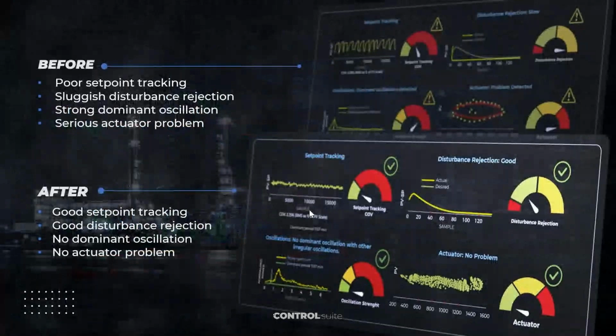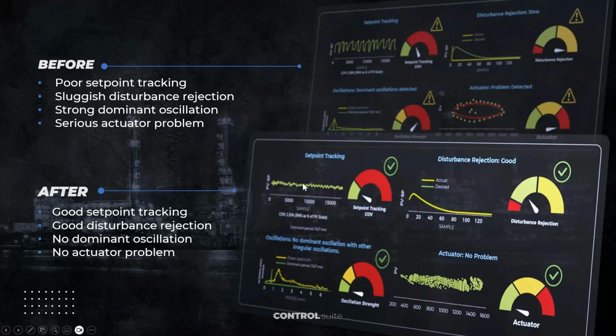Now, we also have copied the gauge set that we were talking about before. And what you see now are the trends of the two performance metrics calculated and historized for a control loop, and showing the saturation problems before and after. Obviously, on the top is the before, and on the bottom is the after. And the red line, these metrics are calculated on a daily basis, so each dot represents the performance metric value on a given day.